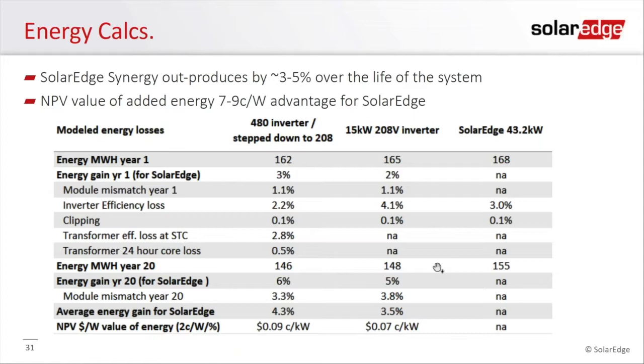So here are the energy calculations that really help put SolarEdge over the top with our Synergy inverter. We're using PVsyst, and we're doing 2 sets of calculations. We do a year 1 calculation, and you can see that SolarEdge has the biggest advantage. The next one would be the 15 kilowatt 208 inverter, where we would have a 2% advantage because of the native efficiency of the inverter, as well as the fact that we're overcoming module mismatch. And of course, we would then have a higher advantage versus the 480 volt inverter, because the 480 volt inverter would have some transformer losses because of the step-down transformer.